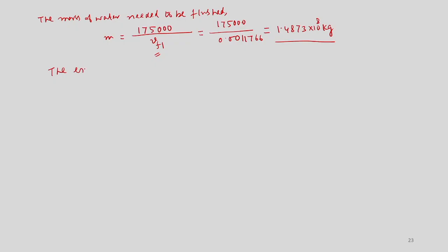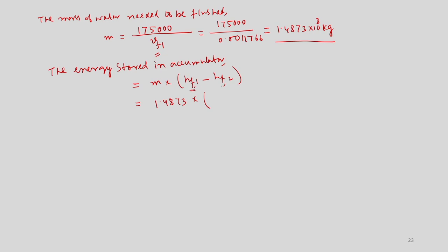The energy stored in the accumulator will be mass multiplied by the enthalpy change HF1 minus HF2. So, this is something like 1.4873 multiplied by. So, we know the enthalpies at 20 bar and 2 bar, which are something like 908.5 and 504.8 respectively.